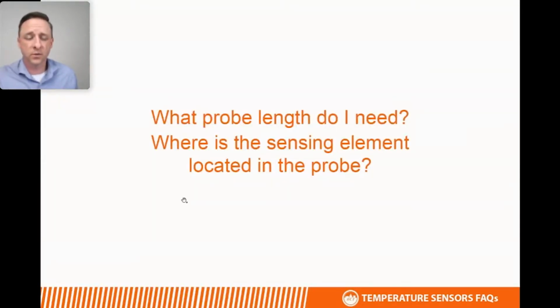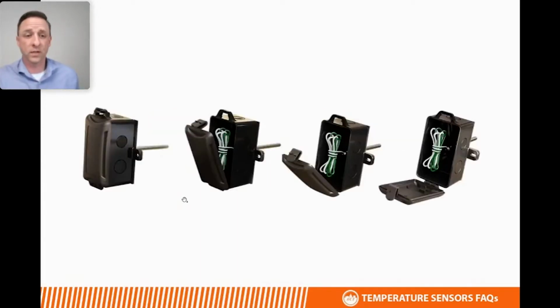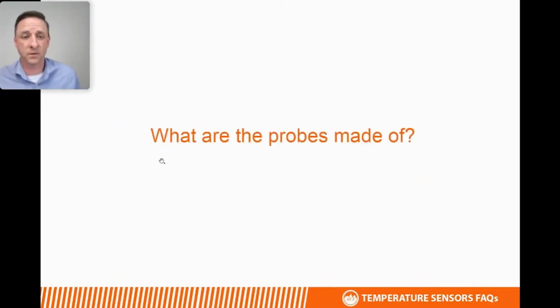Moving on to our duct sensors, the most common question is, what probe length do I need, and along those lines, where is the sensing element in the probe? For all of our probe style sensors for duct and immersion, the sensing element is epoxied into the tip of the probe. So for duct sensors, we recommend you use a long enough probe so that the tip of that probe is in the middle of the airstream. We have probes ranging from 1 inch in length up to 48 inches in length to fit into nearly every size duct that you might be able to think of.